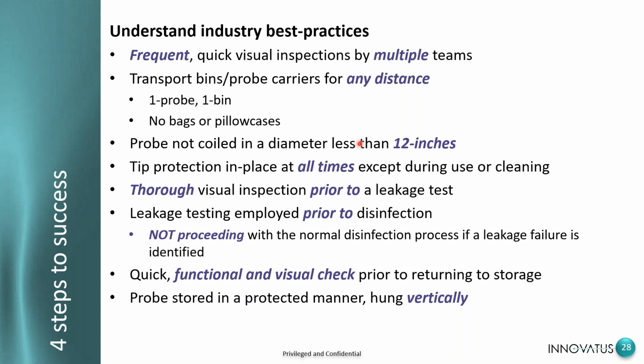Thorough visual inspections. Leakage testing. You see that I have here prior to disinfection. That is absolutely crucial. If you do a leakage test after high-level disinfection, and the probe has a breach, some type of trauma, you will have fluid within that probe. And then when you leakage test, you are now energizing that probe with current, which will blow up that probe, for lack of a better term. So we always want to do leakage testing prior to high-level disinfection.